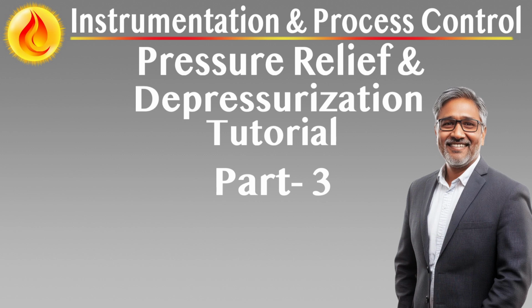The depressurization rate must be sufficient to ensure that internal pressures in vessels and piping do not exceed allowable stress limits, especially during fire exposure. Calculations should demonstrate that the system can achieve the required pressure reduction within defined timeframes, without causing equipment damage or overloading the flare system. Key practices include using recognized methods to evaluate the pressure decay curve and associated vapor flow rates.